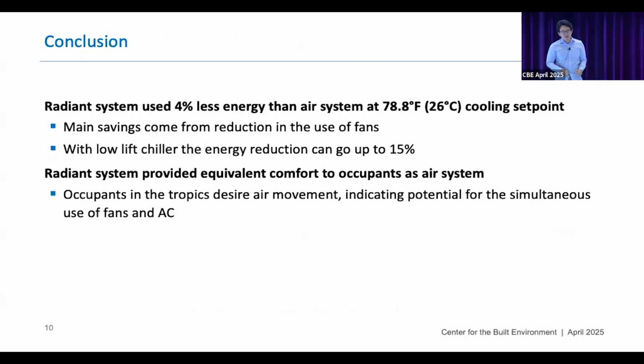So in conclusion, radiant systems reduce energy consumption because we are not delivering sensible heat through air as a medium, and with a low lift chiller we can further reduce the energy by up to 15%. And radiant and air systems provide equivalent comfort to the occupants. For occupants in the tropics, they desire more air movement, and designing with that would definitely reduce the energy consumption and at the same time maintain the thermal comfort.